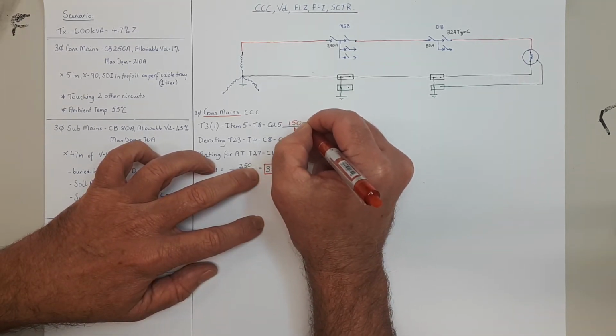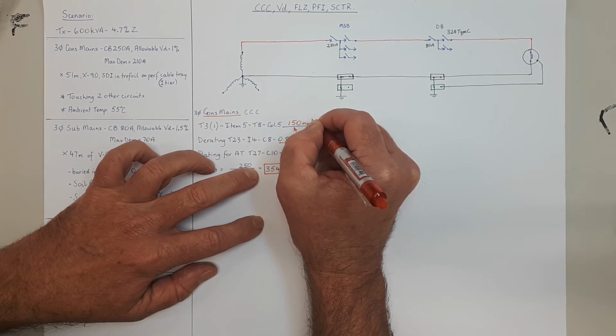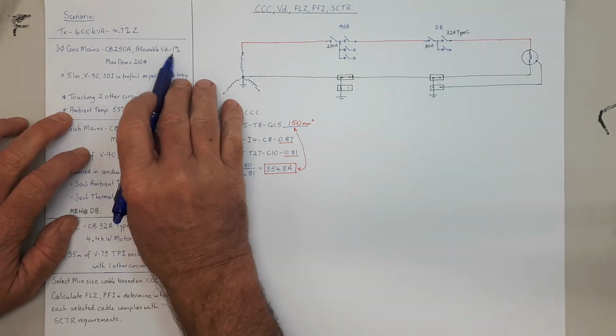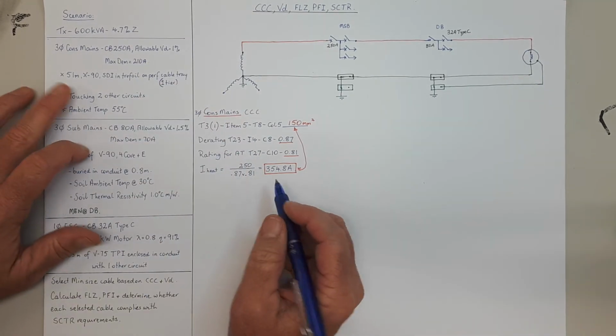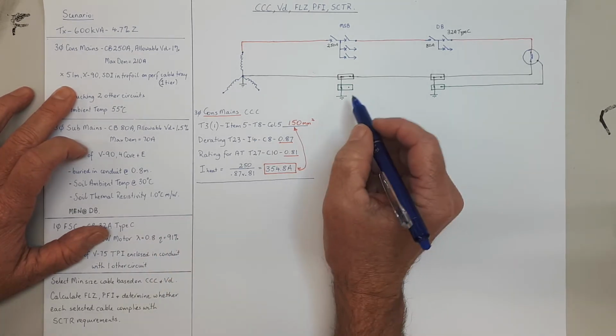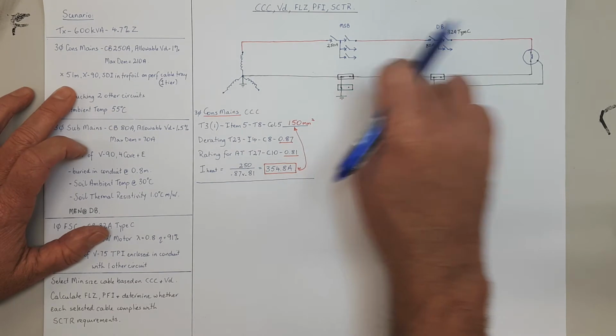But of course we haven't considered voltage drop yet. Now it tells you for the cons mains we're allowing 1% voltage drop because, well, you've got to spread your 5% over the 3 parts of the circuit.